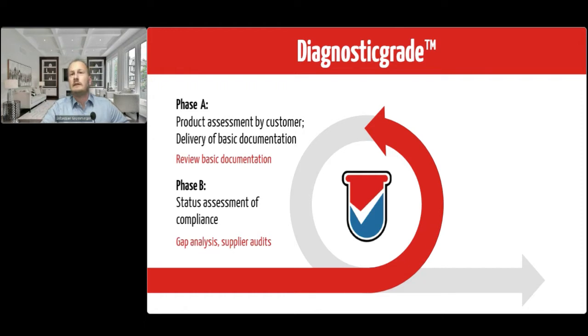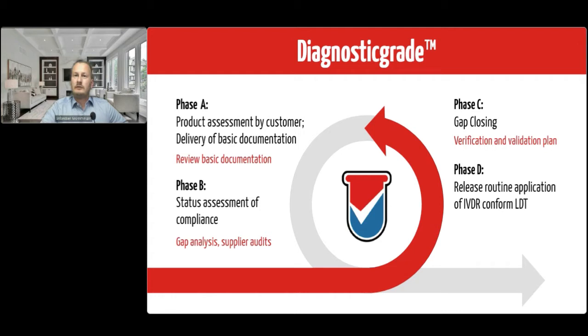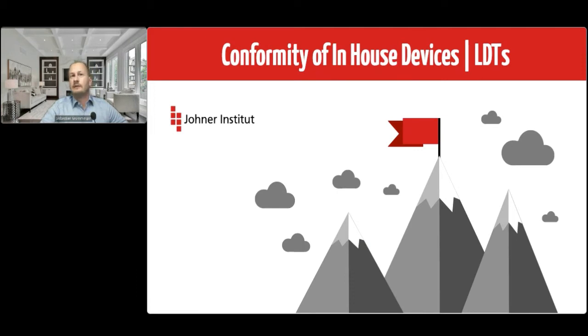And then phase C is the gap closing, where we can provide verification and validation plans and monitor these activities. And in a phase D, where the laboratories release routine application and conform with IVDR with their LDTs, we can provide review of changes and post-market surveillance, take over post-market surveillance activities and perform audits if you wish. And with this, you can reach the conformity of in-house devices and lab-developed tests.